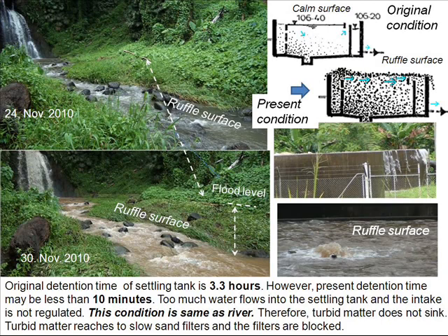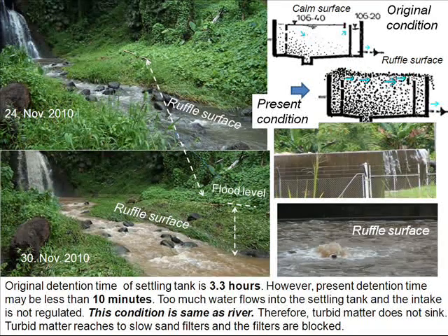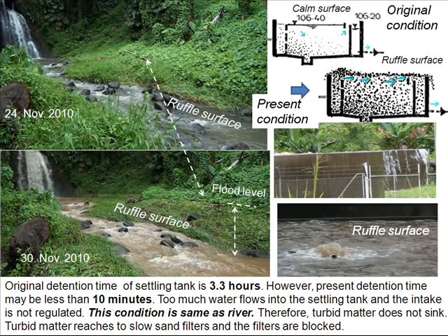The original detention time of the settling tank was 3.3 hours. However, the present detention time may be less than 10 minutes. Too much water flows into the settling tank and the intake is not regulated. This condition is the same as a river — therefore, turbid matter does not sink. Turbid matter reaches the slow sand filters and filter work is blocked.